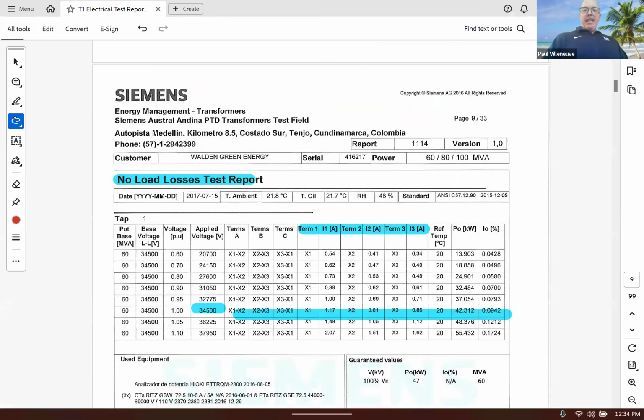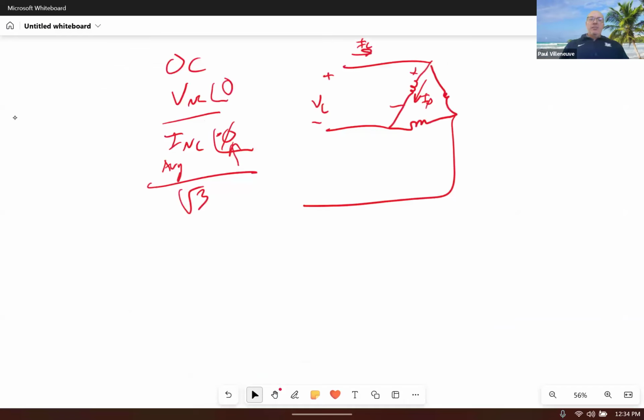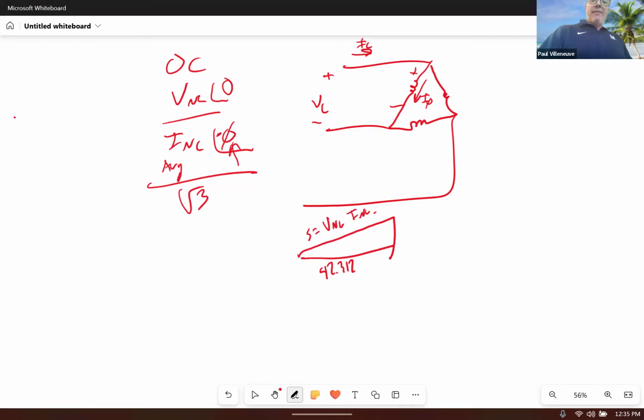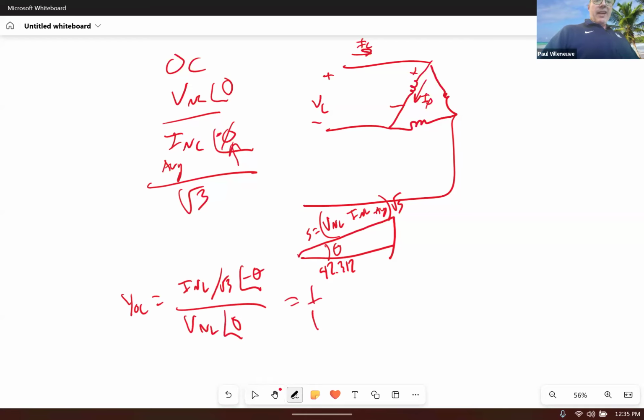The only thing I need to do is solve for theta. Well, I can see that I've got a power of 42.312. That's a three-phase power. I've measured all three phases. So I've got 42.312 for my power triangle. This value of S is equal to V no load times the I no load average. And then I multiply that whole thing by the square root of 3, right? I'm looking at the average of the I no load, not the phase current, not divided by the square root of 3. And when I do that, I end up with theta there. Okay. And when I've got that, now I can solve for my Y open circuit, which is I no load divided by the square root of 3 at an angle of minus theta, divided by V no load at an angle of 0, and that's equal to 1 over R sub C plus 1 over J X sub N.